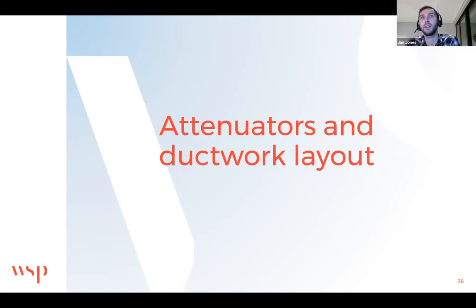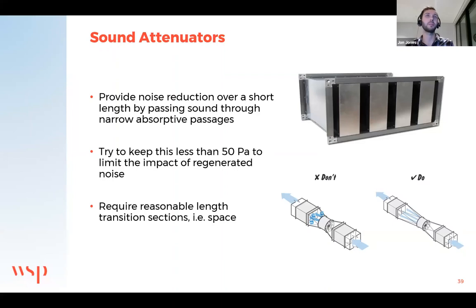Attenuators and ductwork layout. So a little bit on sound attenuators. This is very mechanical based, I'm afraid, for other specialists, but it's probably where the largest interface between acoustic consultants and mechanical consultants is generally. Sound attenuators, I'm sure many are familiar with, basically reduce noise in a duct as it travels down the ductwork, and they do so with restricted airways and absorptive passageways. So in between these, behind the steelwork, there's a whole load of acoustic absorption that absorbs the sound as it passes through these airways, which are quite restrictive, and by the time it comes out at the other end, a proportion of it has been absorbed within the attenuator.